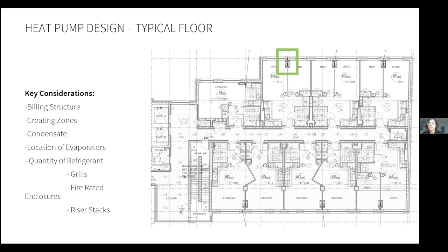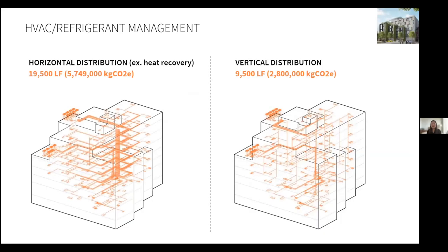Careful coordination of condensate lines is important, as well as location of evaporators, typically wall mounted in our projects, but we're looking at other systems which Joe and Sara will touch upon. And finally, refrigerant management and efficiency is crucial. Again, on the Rise, Julie's team was able to compare different layouts of refrigerant lines, which is pretty telling. So these are diagrams of the Rise showing a horizontal versus vertical distribution of refrigerant lines.